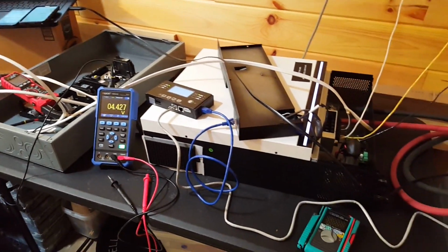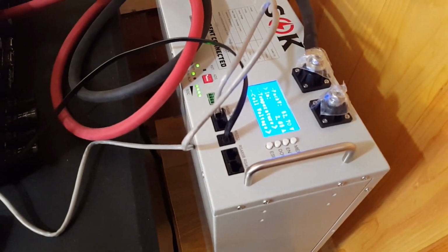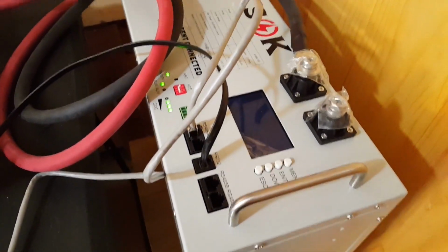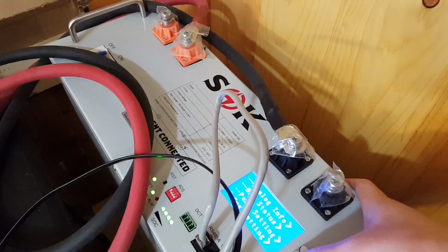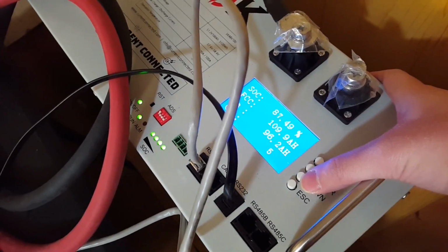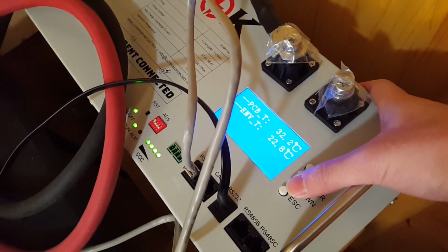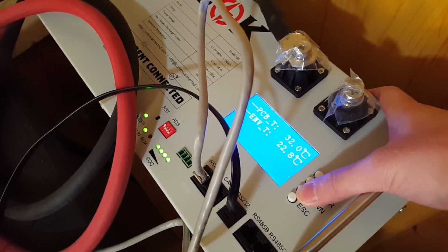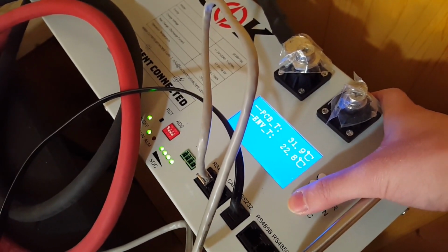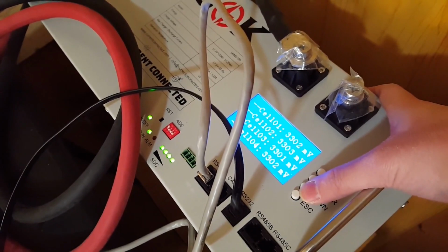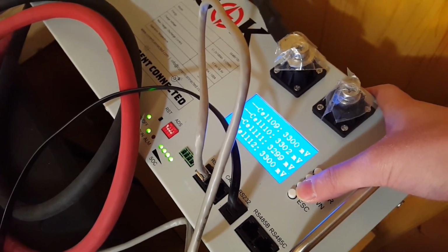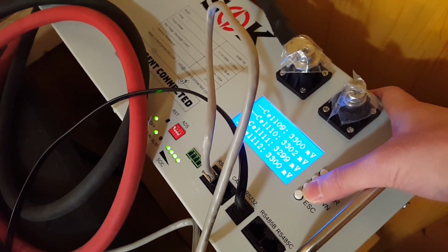Alright, for this next test, we will look at the maximum discharge current for the battery. We'll see if it can actually sustain 100 amps. Let's check state of charge right now, 87%. Temperatures, 32 Celsius for the BMS, around 14 to 15 for the batteries. The cell voltages are exactly 3.3.